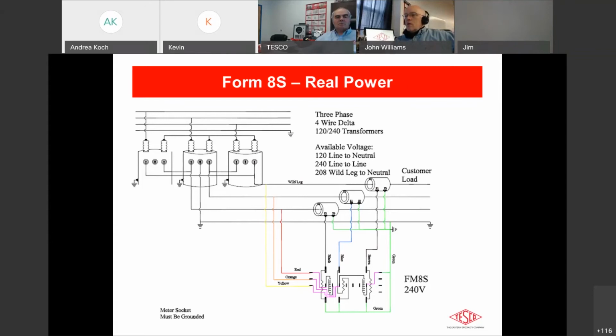The self-contained mirror of this, I guess, is the 15S, and we'll talk about that in a minute. But again, as you can see, as we go through these, we're getting more and more complex in the number of elements and the number of connections and so forth, and the applications in the field. Typically, as far as I know, 90+% of the application for the 8S meter is for the higher current applications for a 4-wire delta.